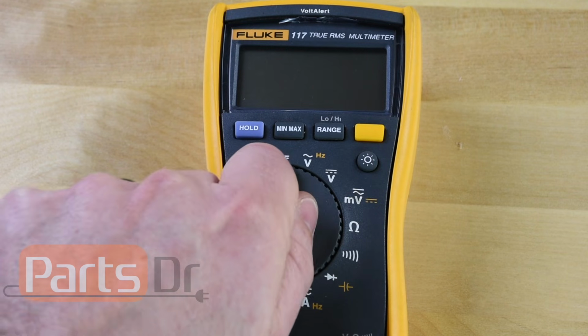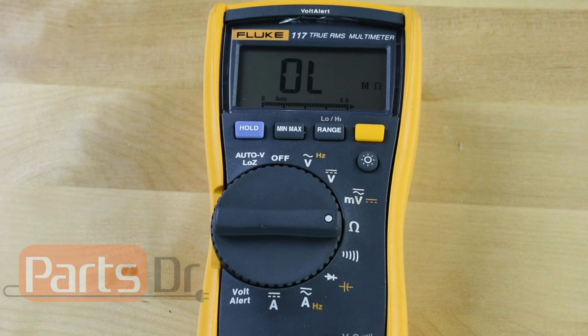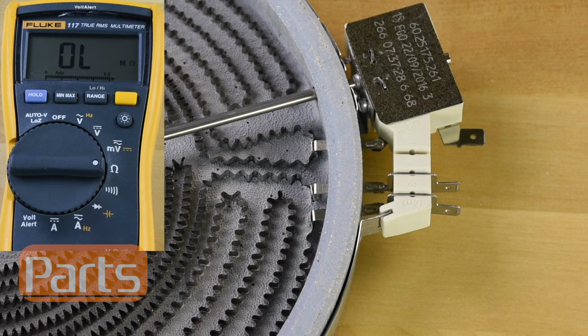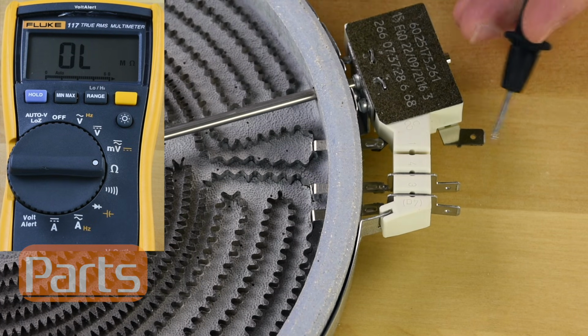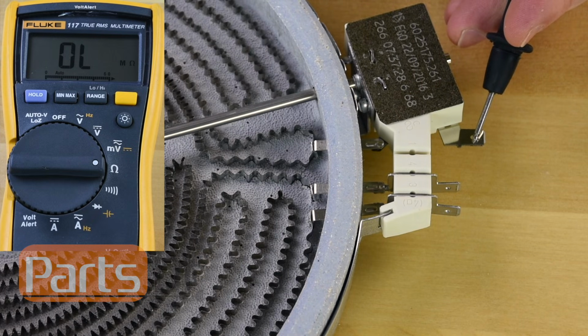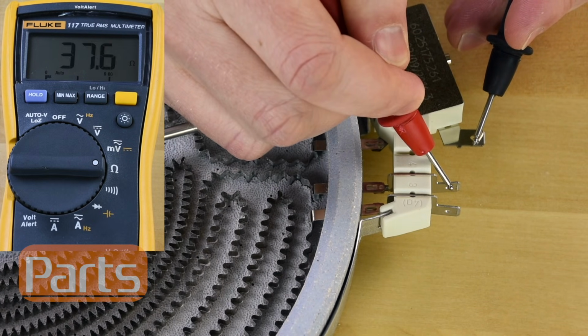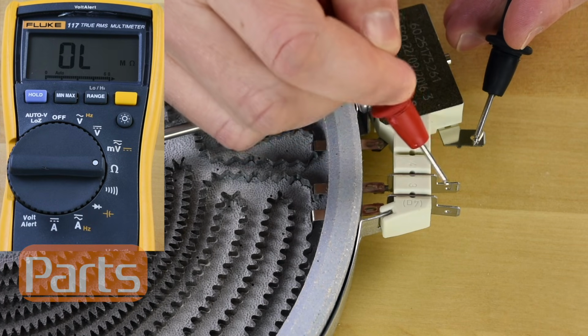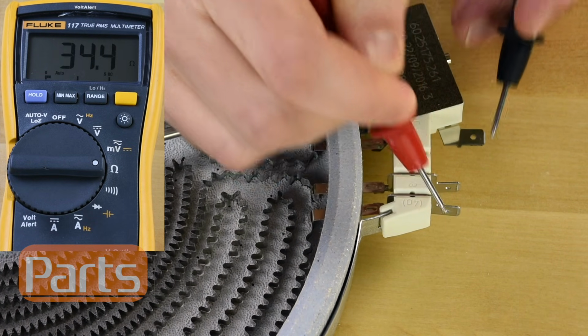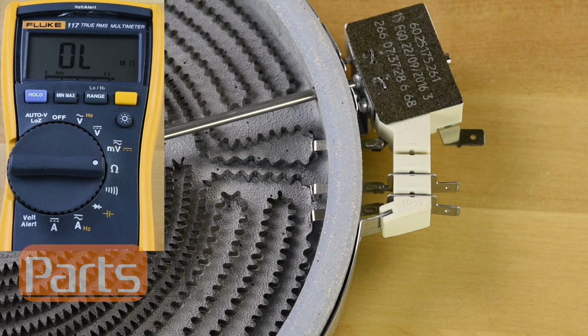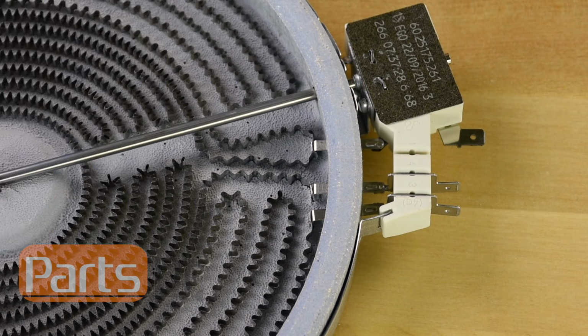If your multimeter does not have a continuity setting, then you can do an ohm test. If you have an auto-ranging multimeter, then turn it to the ohm setting. If you have a manual ranging multimeter, then you'll need to set the meter to the lowest ohm setting. Place one of the probes on the common terminal and the other probe on one of the other terminals. Next, repeat the same process on the other terminals. You should get an approximate reading of 10 to 100 ohms on each of the coils. If the display on the meter does not change or your ohm reading is far off from that, then you have a bad heating element.